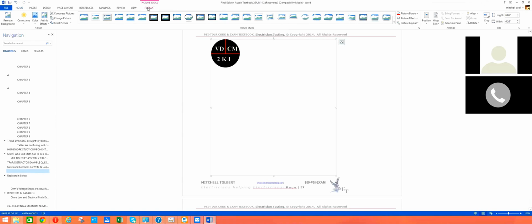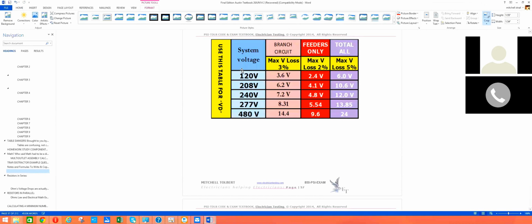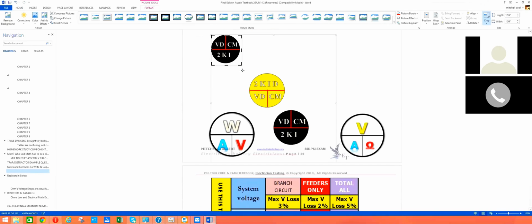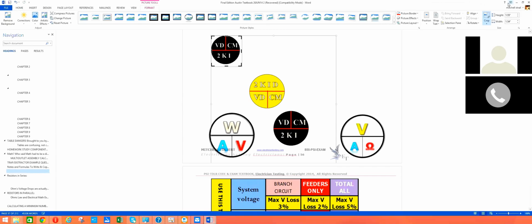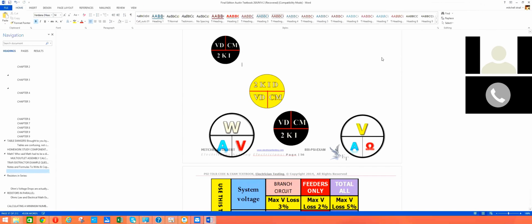They give you the FLC value of that motor. Now, is there somewhere that you can think of in your code book that an FLC value and a horsepower rating might be able to give you a branch circuit rating? Let's see. It's something to do with 746, right? And that was the confusing part on them voltage drop questions. I didn't know, when you're dealing with horsepower, if you times by the 746.